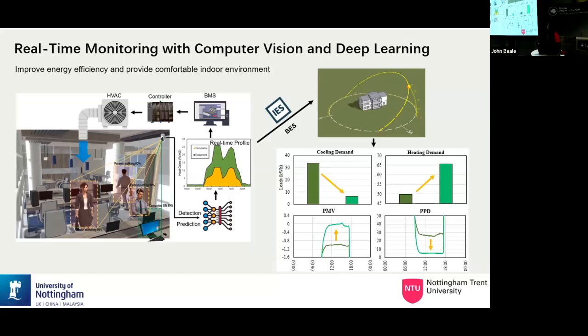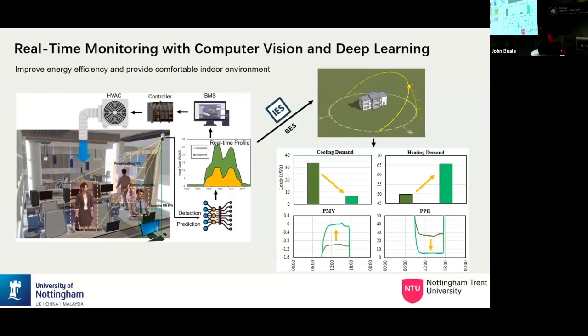To enhance the indoor comfort level and achieve better energy efficiency, we developed a framework using computer vision and deep learning to estimate heat emissions in indoor spaces. When people perform different activities, when there are different numbers of people, or when different numbers and types of equipment are in use, the heat emission in the indoor space varies. Once we get real-time information from the indoor space, we input it into building management systems to achieve demand-driven control for heating, cooling, and ventilation.